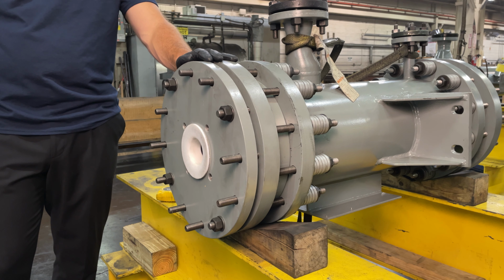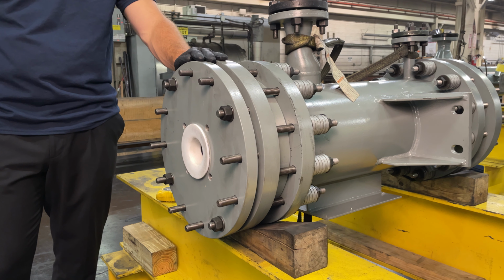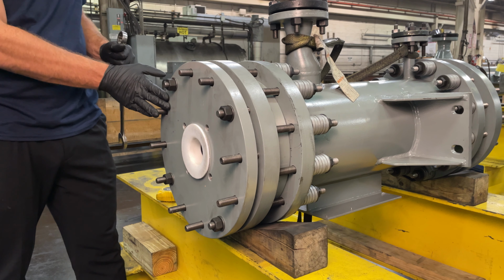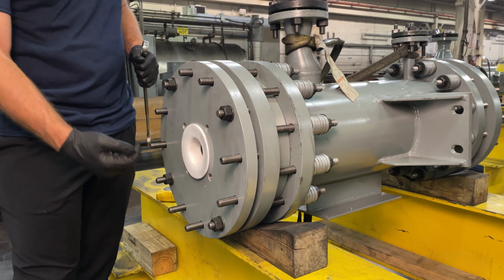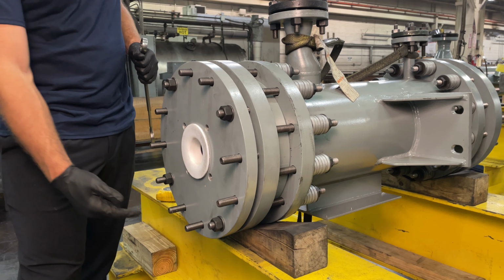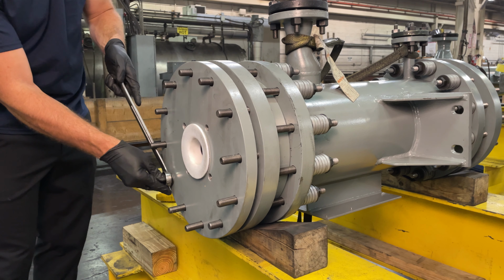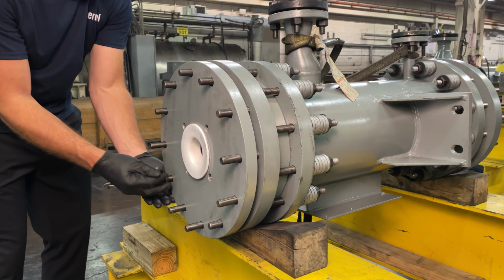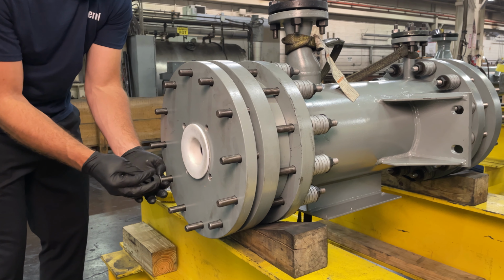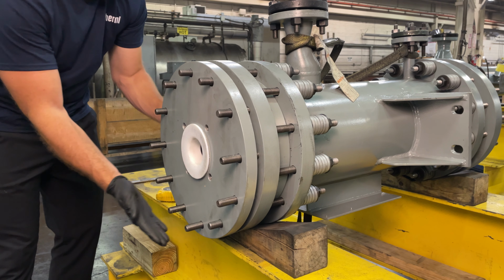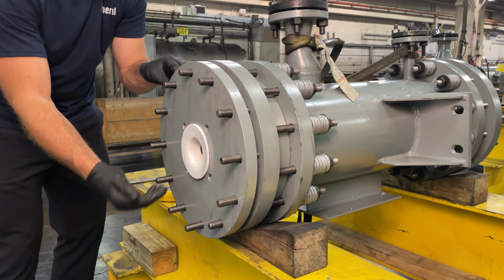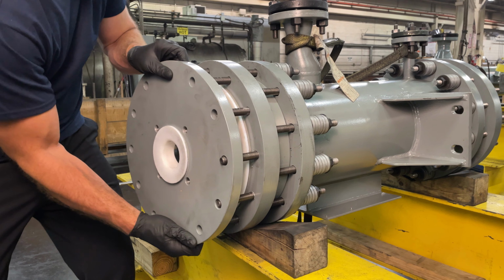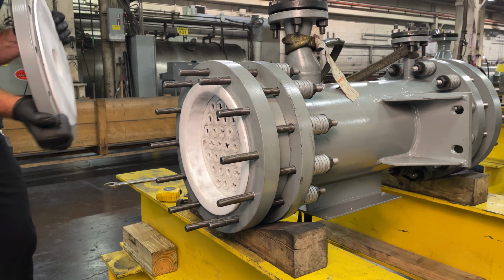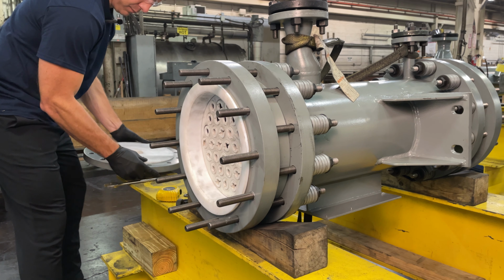Once you've flushed your unit and feel safe to disassemble, you'll want to first remove the clamp plate. You'll remove the bolts in a reverse radial pattern. We've already got started here, so I'll just finish the last few. When the clamp plate is removed, the PTFE liner surfaces are exposed. Care should be taken not to damage the liner face, particularly where the gasket serrations are.